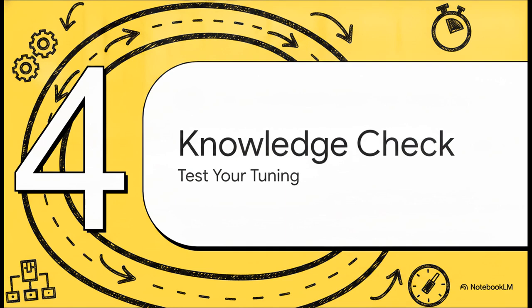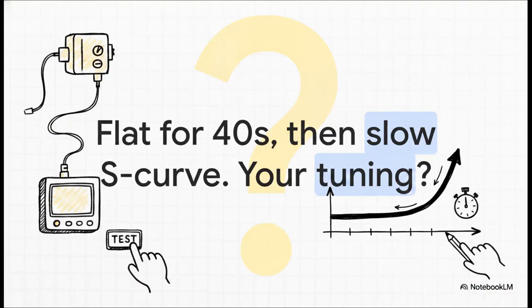All right, time for a loop tuning knowledge check. Let's pause for a super quick interactive moment to test your floor knowledge. Picture this scenario. You're out on the floor commissioning a brand new loop. You step test the controller, and you're just staring at a totally flat trend line on your screen for 40 long seconds. You're probably starting to wonder if the sensor's completely busted. But then, finally, it starts this slow S-curve climb. Based on everything we've covered today, how are you going to approach tuning this thing?